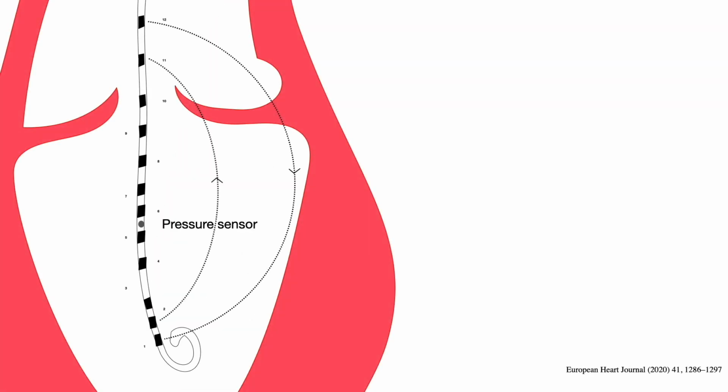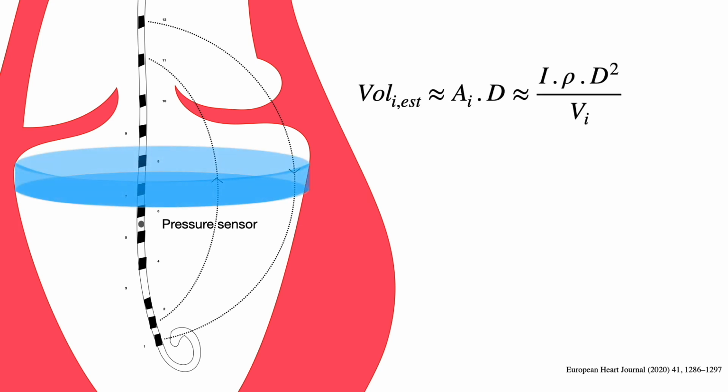Pressure volume loops are measured by putting a PV catheter inside the ventricular chamber by a transaortic or transseptal approach. The basic principle is that there are 12 electrodes on the catheter, and the proximal and distal electrodes generate an electrical field. The device measures the volume of the LV cavity by dividing it into imaginary cylindrical segments around each electrode.